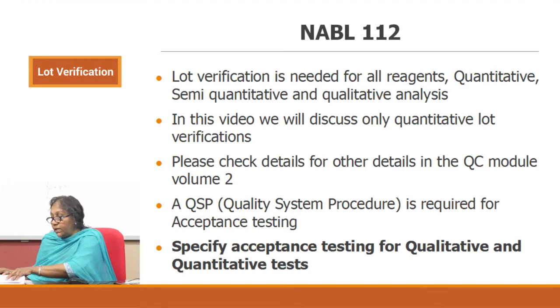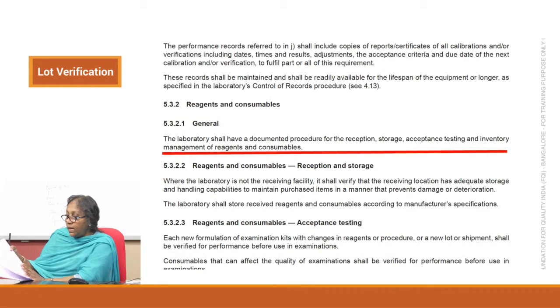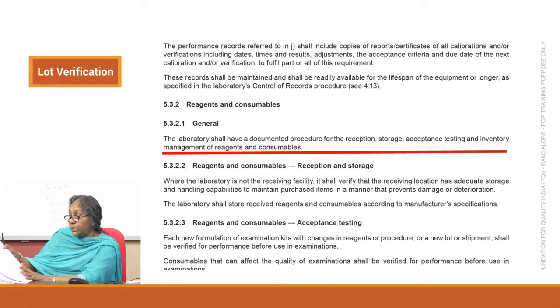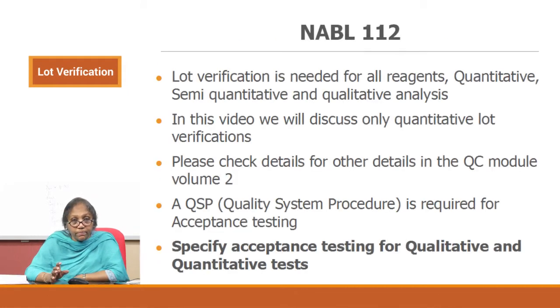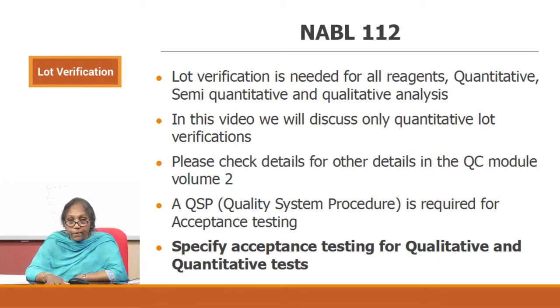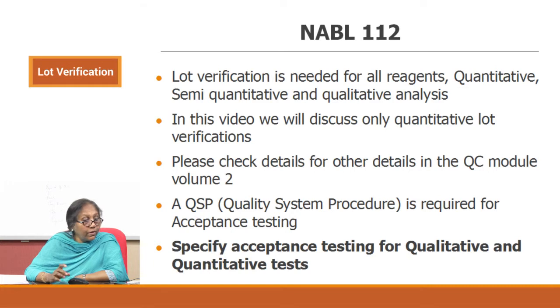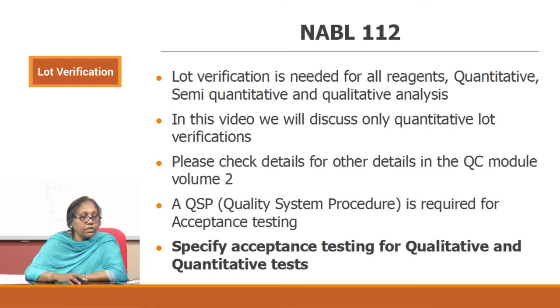If you look at 5.3 again, the laboratory shall have a documented procedure for the reception, storage, acceptance testing, and inventory management. So acceptance testing is part of the QSP that you would write under 5.3. The mechanisms should be defined for both quantitative and qualitative tests — and what those mechanisms are, the acceptance limits — all should be defined in your QSP.